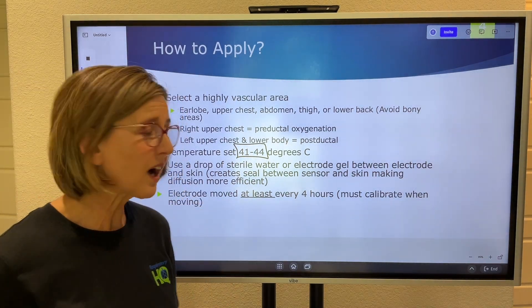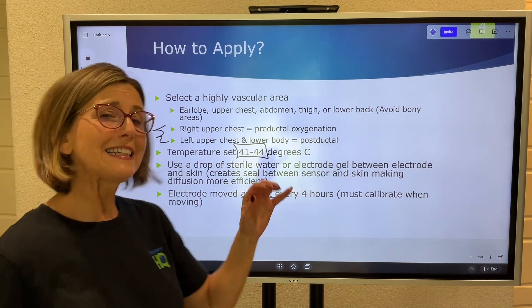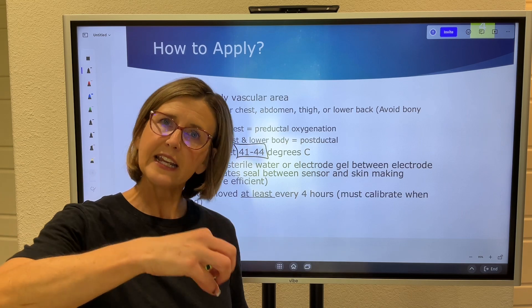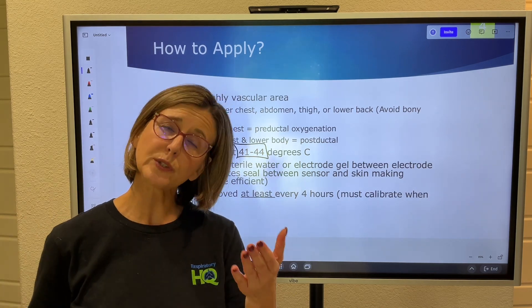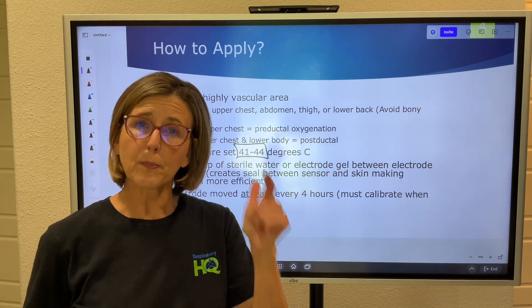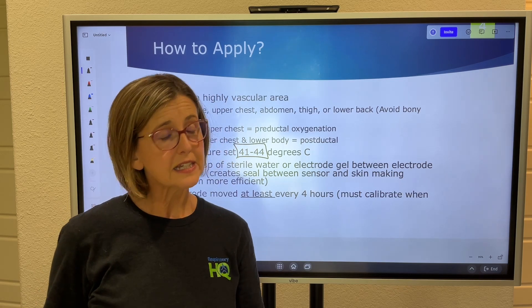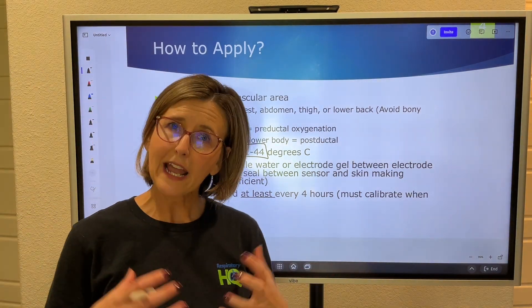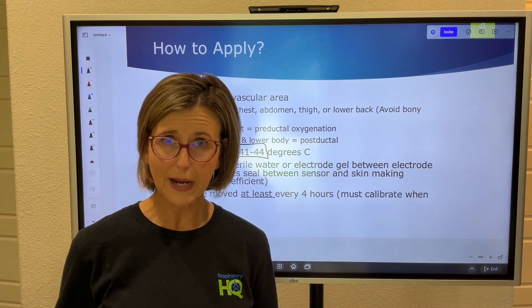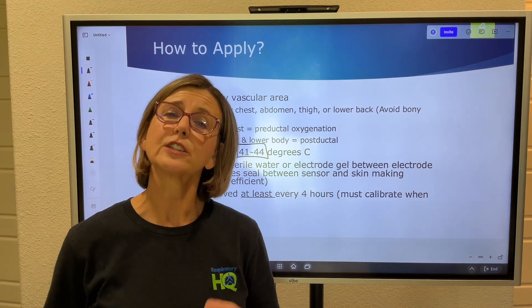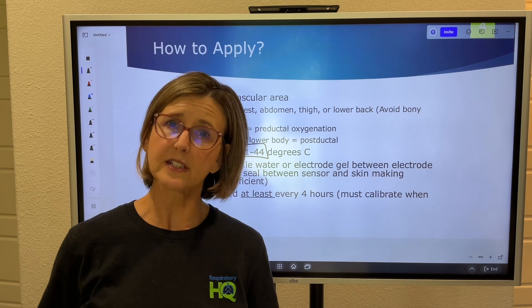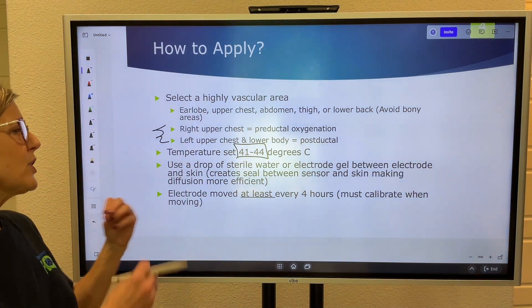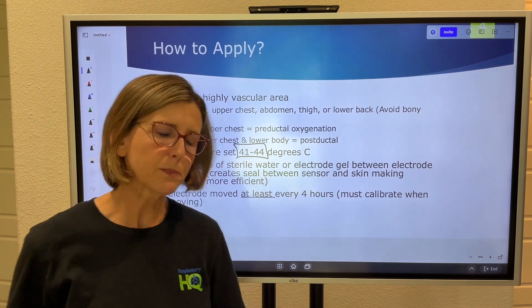Because the electrode is hot, it must be moved at least every four hours to prevent burns. The more premature the baby, the thinner the skin, so you may need to move it more frequently. Monitor the site for redness — if it's very red after four hours, move the sensor more often. Remember: whenever you move the sensor, you must recalibrate it.